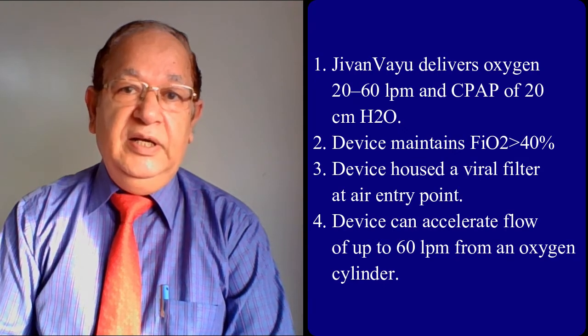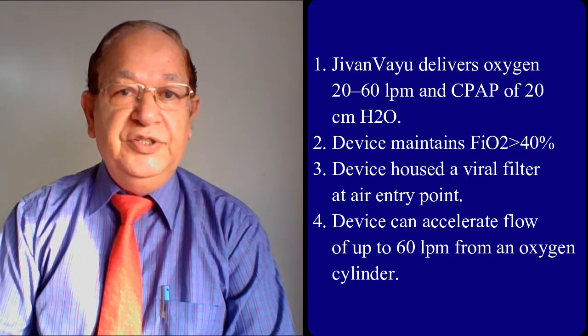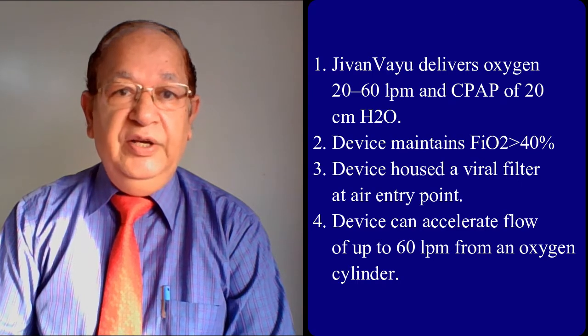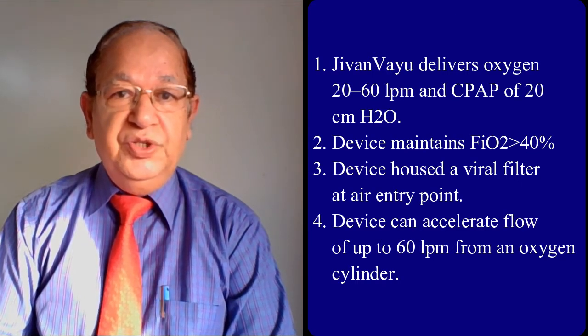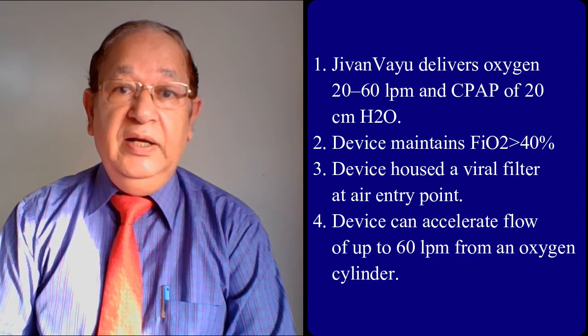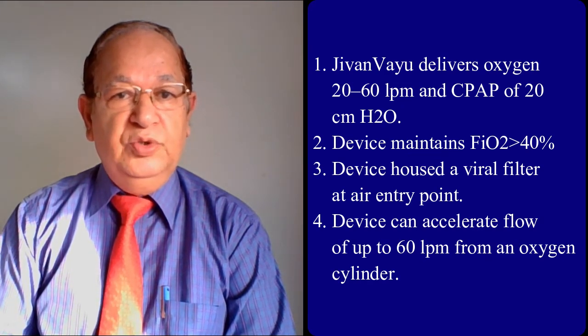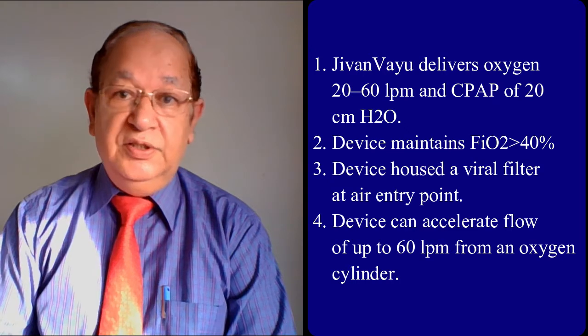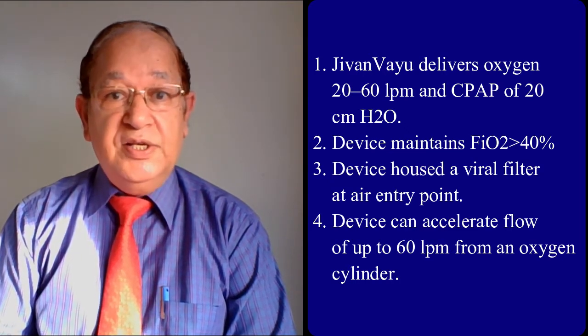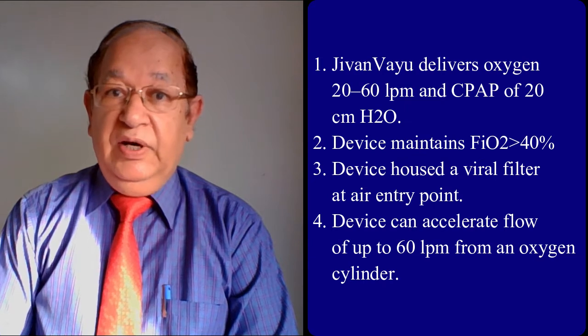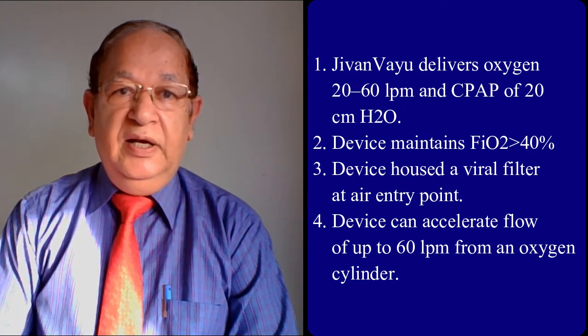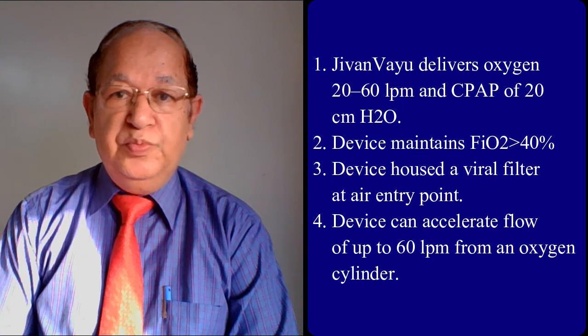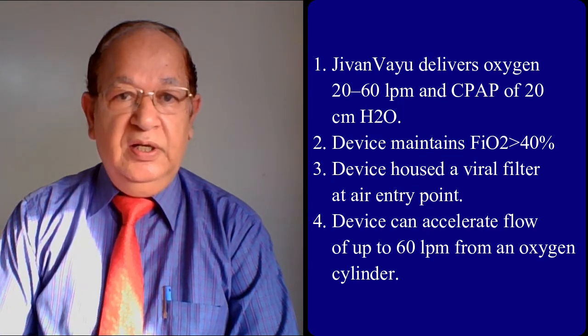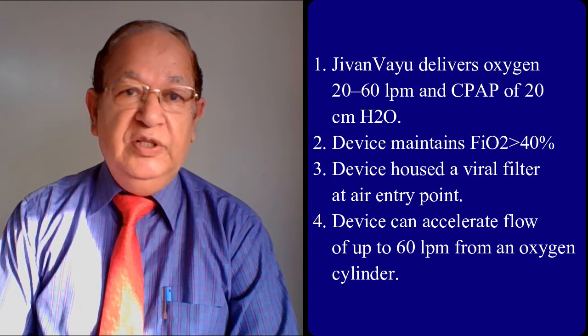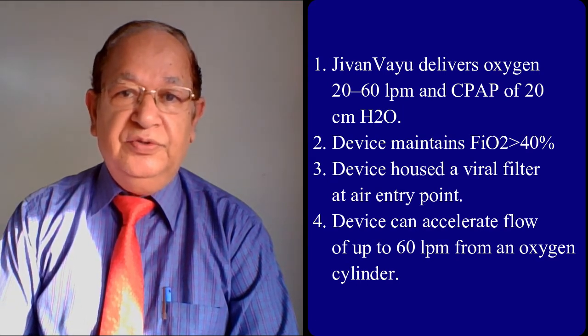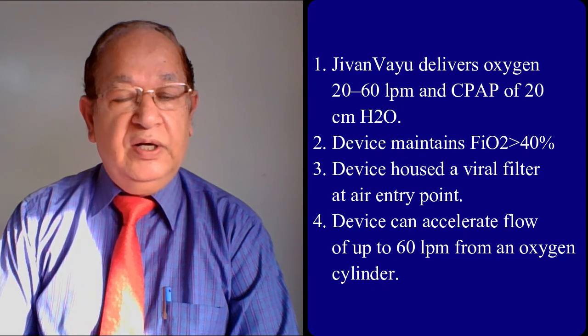The team developed a 3D printed device, named it Jeevan Vayu, which can deliver high flow oxygen from 20 to 60 liters per minute while maintaining a continuous positive pressure of up to 20 centimeters of water, resulting in a low cost and accessible CPAP therapy. The device is designed to maintain an FiO2, that is fraction of inspired oxygen in the gas mixture, of above 40% with a positive end expiratory pressure of 5 to 20 centimeters of water.